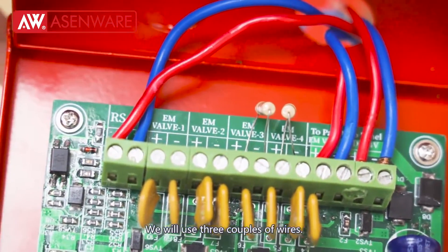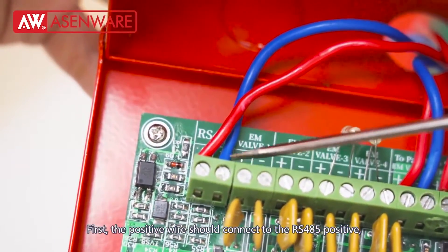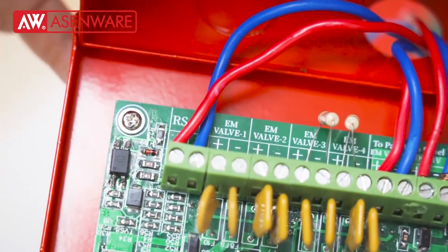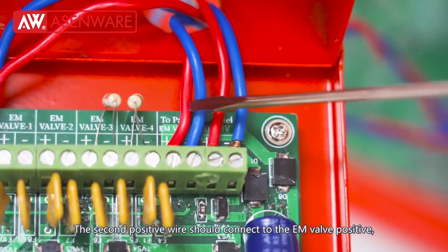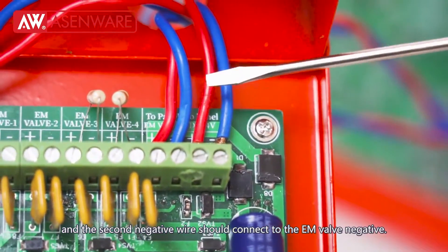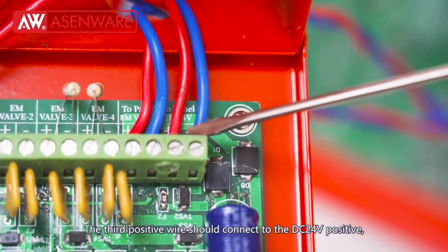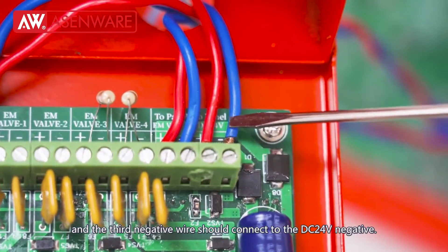We will use three pairs of wires. First, the positive wire should connect to the RS485 positive and the negative wire should connect to RS485 negative. The second positive wire should connect to EM valve positive and the second negative wire should connect to EM valve negative. The third positive wire should connect to DC24 voltage positive and the third negative wire should connect to DC24 voltage negative.